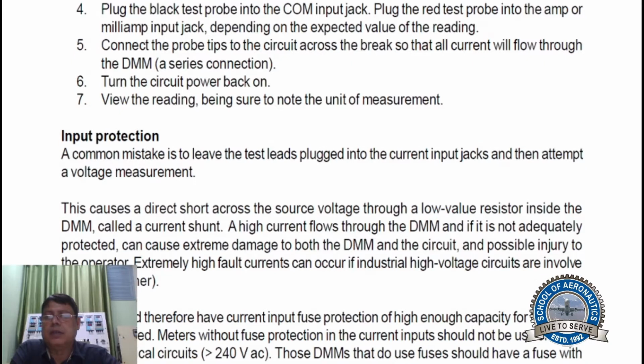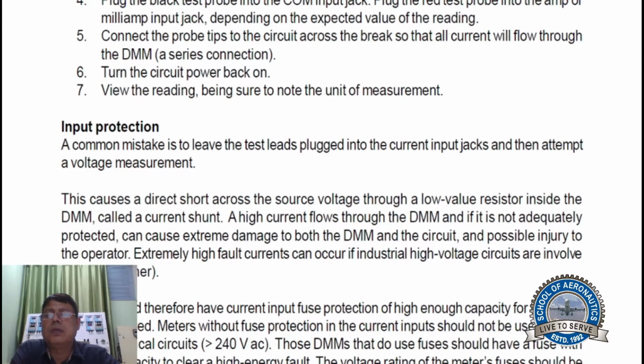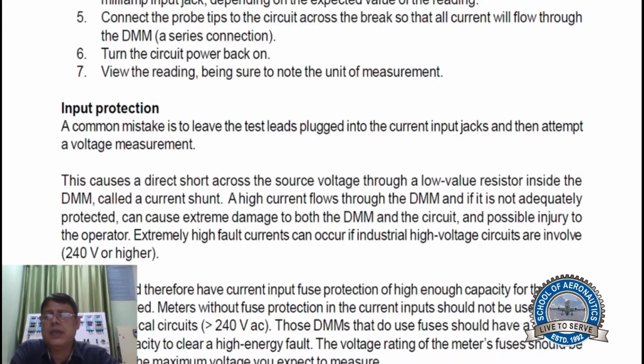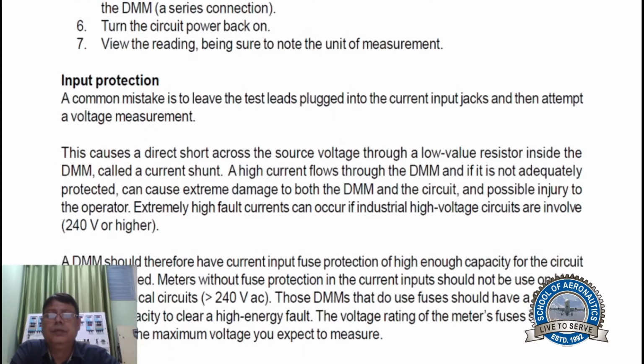Input protection. A common mistake is to leave the test leads plugged into the current input jack and then attempt a voltage measurement. This causes a direct short circuit across the source voltage through a low value resistor inside the DMM, called a current shunt. A high current flows through the DMM, and if it is not adequately protected, can cause extreme damage to both the DMM and the circuit, and possibly injure the operator. Extremely high fault current can occur if industrial high voltage circuits of 240 volts or higher are involved.